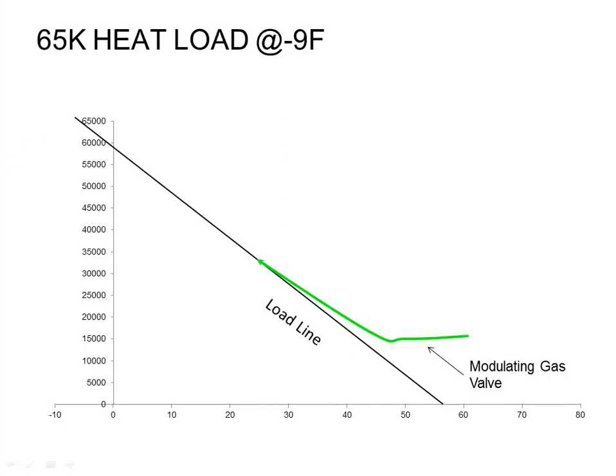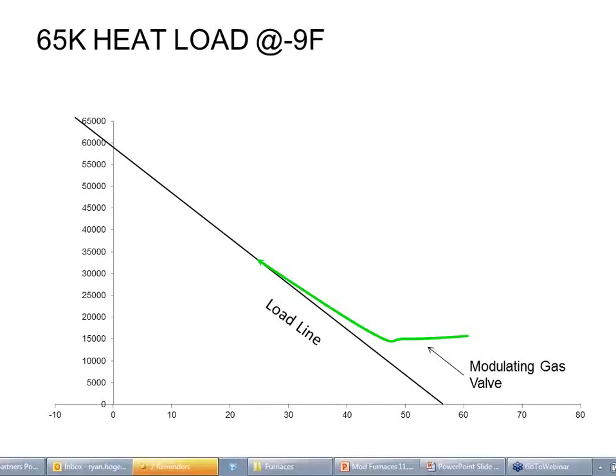So I just need to track the difference between indoor temperature and indoor temperature desired, my set point. This is why we need to use the Evolution Connect control or the Infinity Touch control with this furnace, because a regular thermostat doesn't know any of this stuff. He may know the set point, he may know the current temperature, and he may know the deviation, but he can't tell our furnace that. All he can tell our furnace is, I closed the W1 relay for first stage heat. I closed the W2 relay for second stage heat. That's all the regular thermostat can do. He can't tell us how much heat he wants. He can just say, I want a little or I want a lot, but he can't tell us exactly how much.